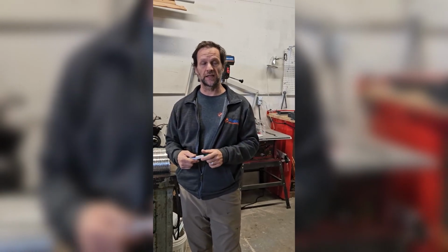The only way to find out the actual run, see how this duct goes inside, and see its condition inside, is by using a video camera. You either insert it through the side where the dryer is, or from the outside, and that way you scope the system and get a pretty good picture of what the system is like, what the damage is, what condition it's in, and eventually what needs to be done to fix it.